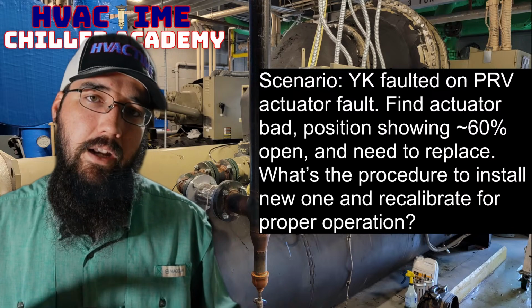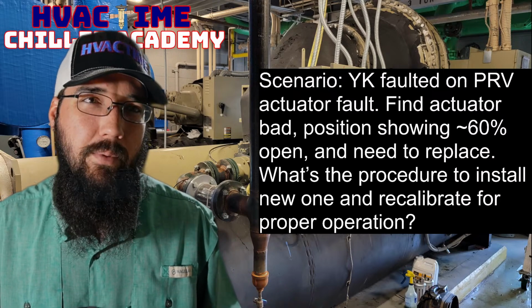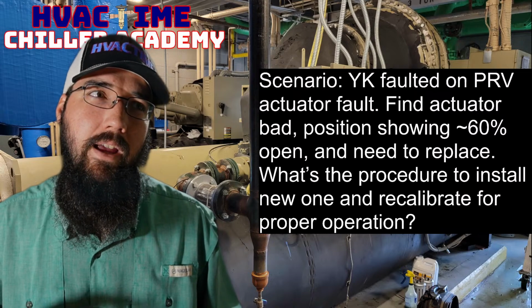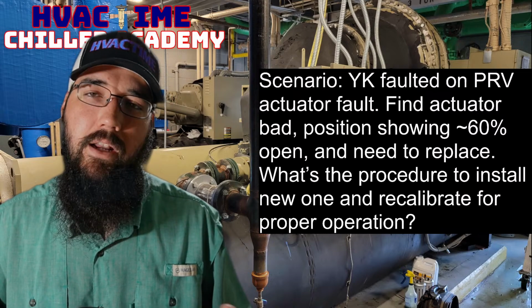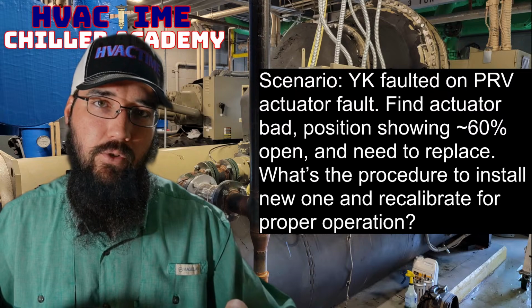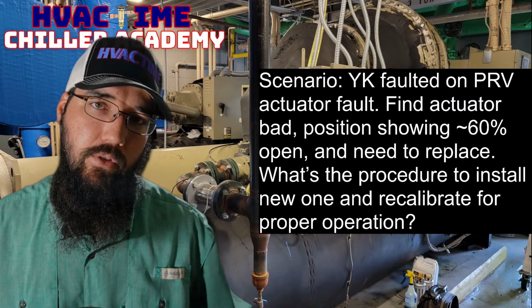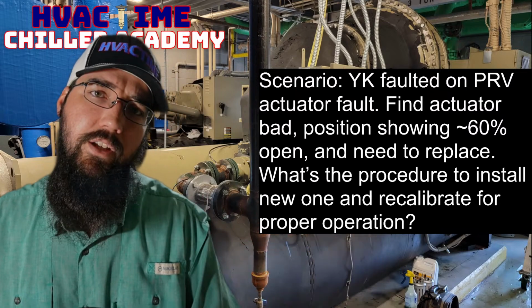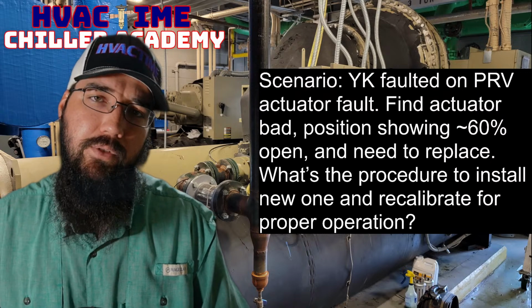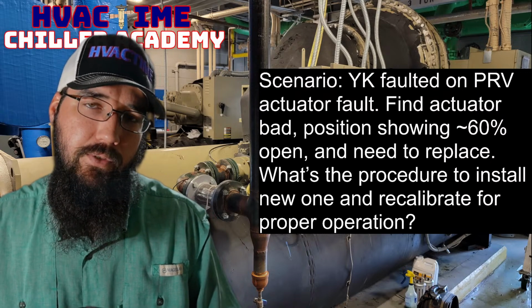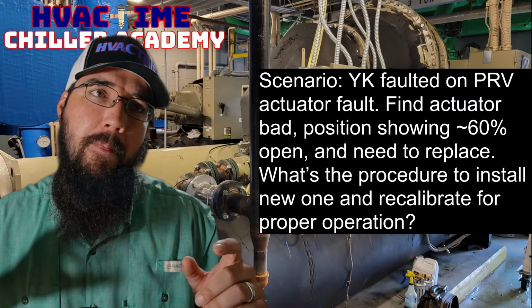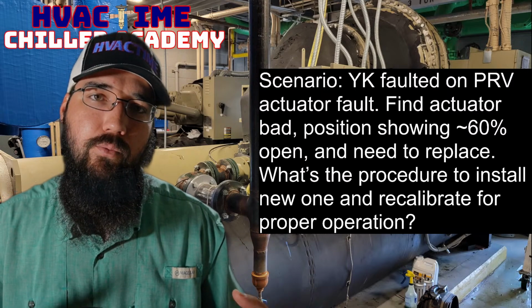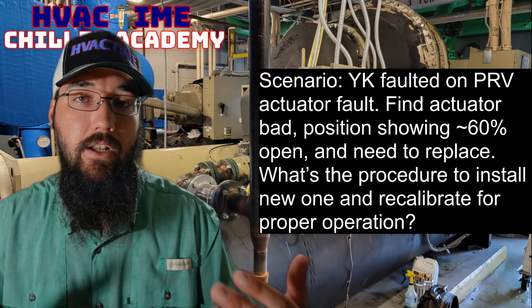I've calibrated mine to full open. I'd have to go back to the manual to verify exactly how it says to calibrate, but that's how I've done mine intuitively - calibrated to full open, moved the armature shaft to a full open position, moved the actuator to a full open position, set it there, and then verified operation, letting it go through its thing.